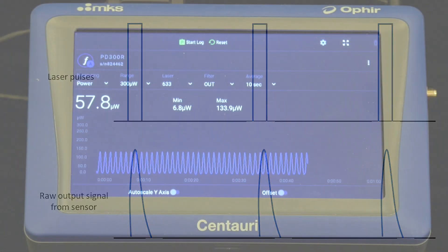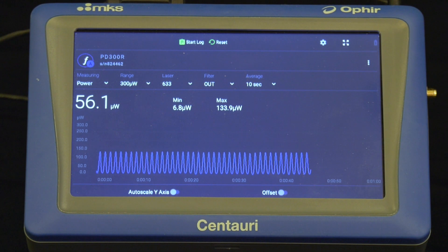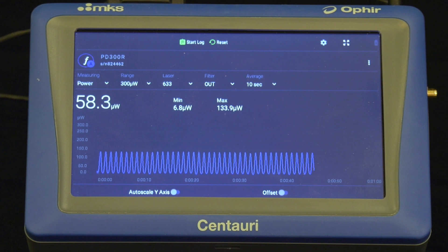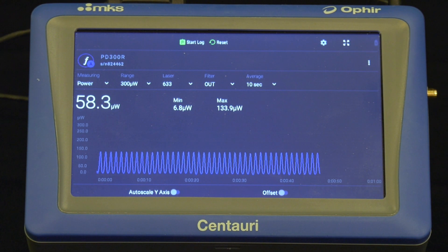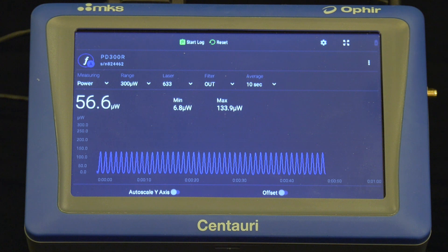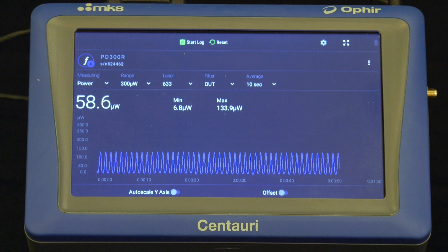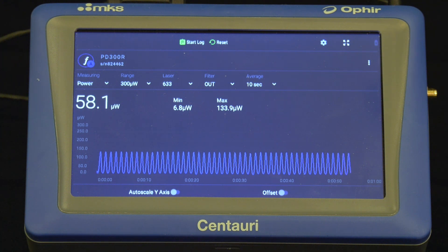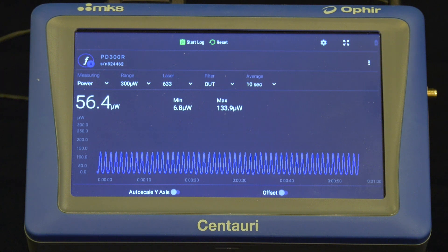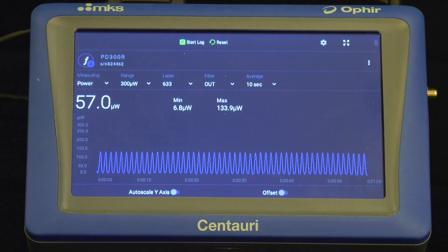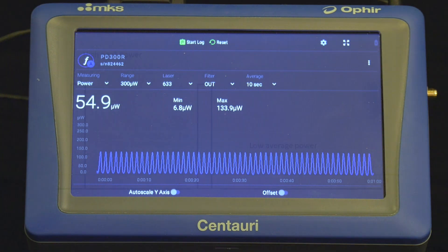Two problems can result from this. First, the low pulse frequency can beat with the sampling rate typical of laser power meters. For example, a typical Ophir meter samples a power sensor's signal at 15 hertz. If the beam is pulsed at, say, 14 hertz, the readout will suffer from a 1 hertz beat frequency that'll make it very difficult to get a proper reading.